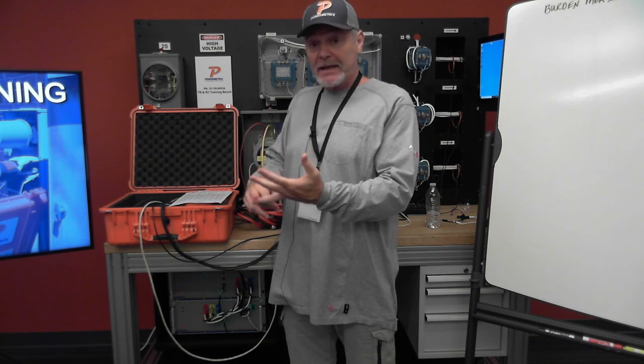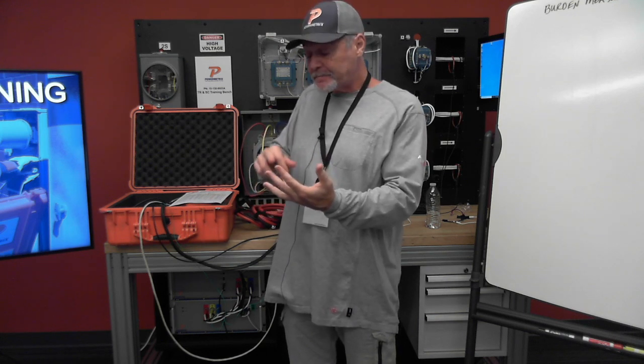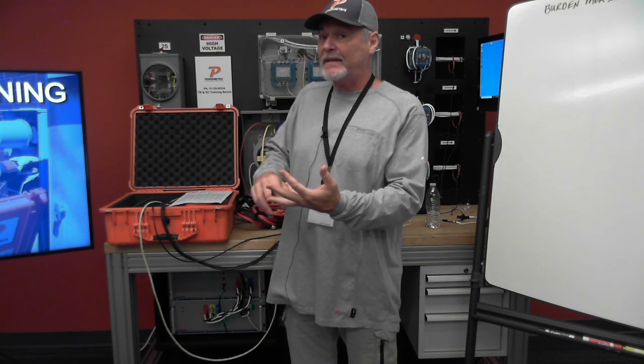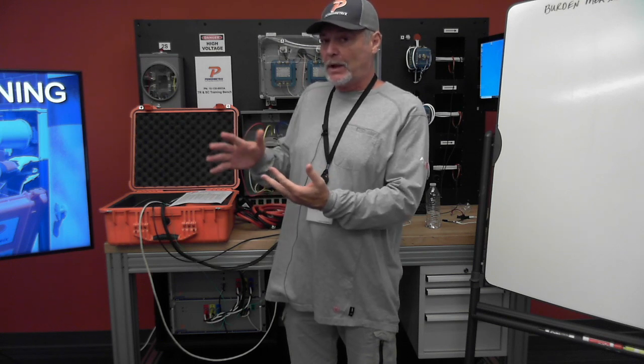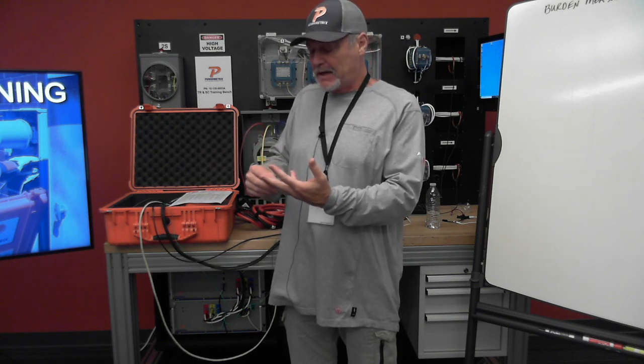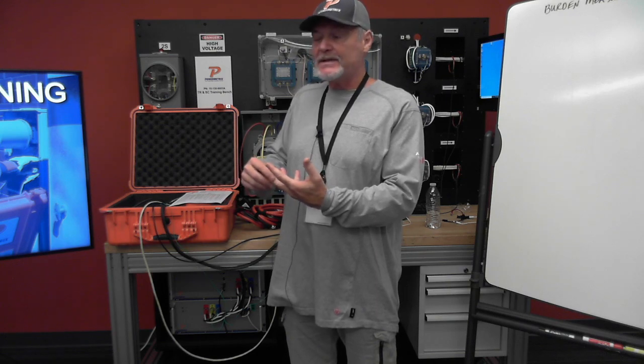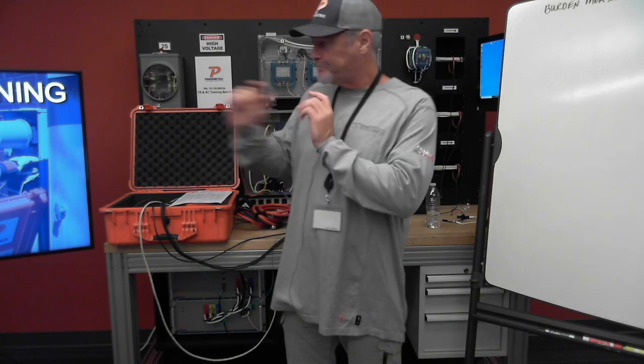We tested the meter, but if you remember, the meter came out like 99.5 something, so it was a little low to what we would consider a pass. That's already got us a little bit curious. So now we're going to see what happens when we get ready to test the CTs.